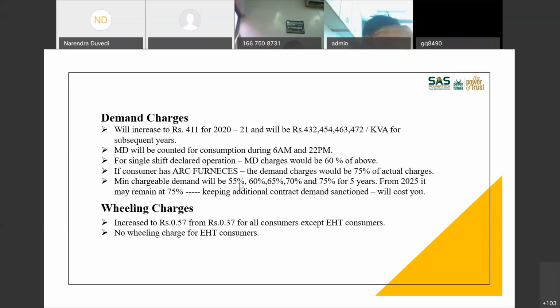Now the reason behind this is a survey done with all the consumers. MSEDCL found that about 40% of the consumers use only 50% of the demand. Once MSEDCL or any utility company sanctions you a contract demand, legally they are bound to supply you that much of demand anytime you ask for it. So they have to block their capacity to some extent. They cannot depend on diversity factor, and the end result was their infrastructure was getting less utilized.